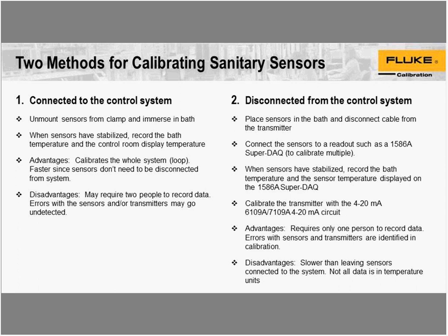So the advantage of this system is that you are calibrating separate modules or separate components of a system. If there's a problem with one of those, you can isolate it and determine where the problem is, whereas in a loop calibration, you may not see the problem that's happening with the probe or the transmitter itself. The disadvantage here, though, is it takes a little more time because you're doing two separate calibrations in essence.